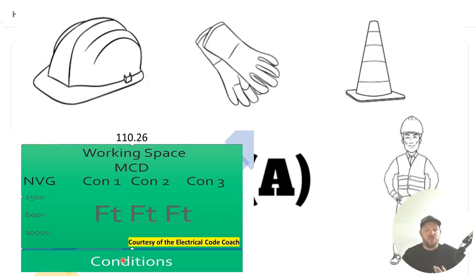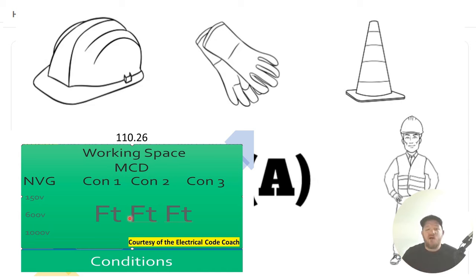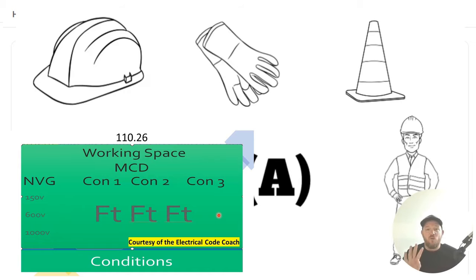So this one, we need to first come to our nominal voltage, which is the middle column. Then we need to slide all the way over to condition three. And that's where we're going to find this four foot requirement.